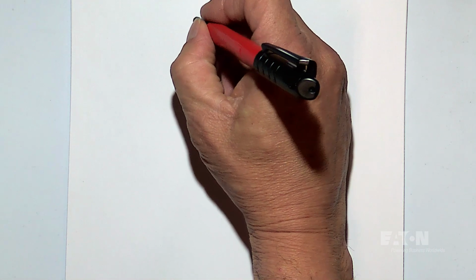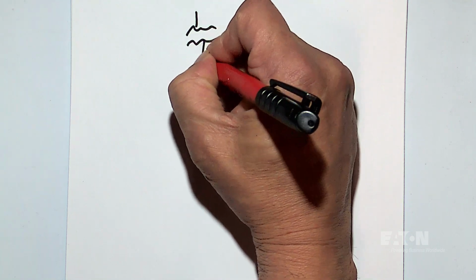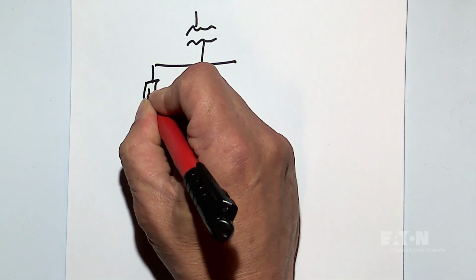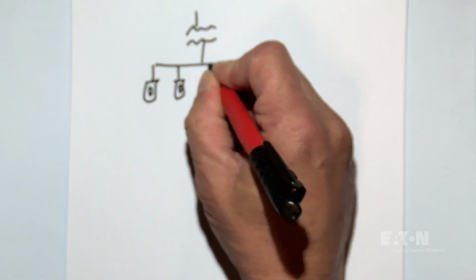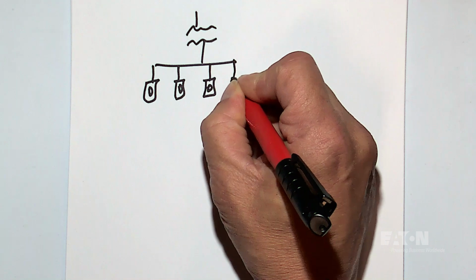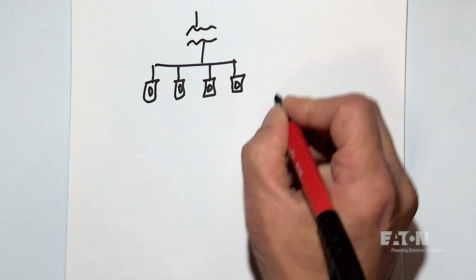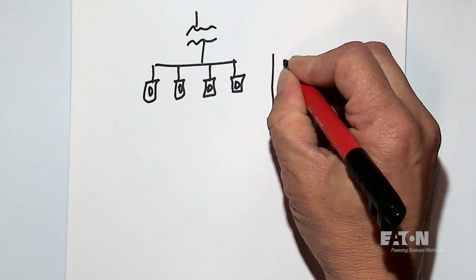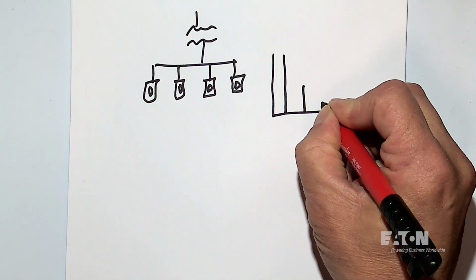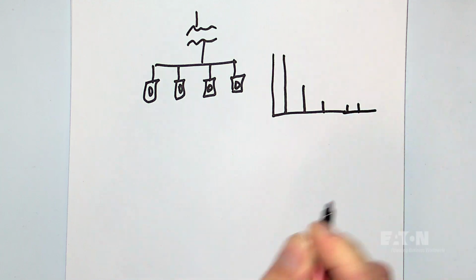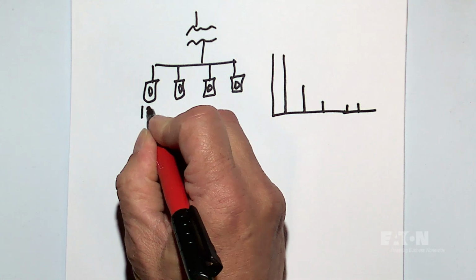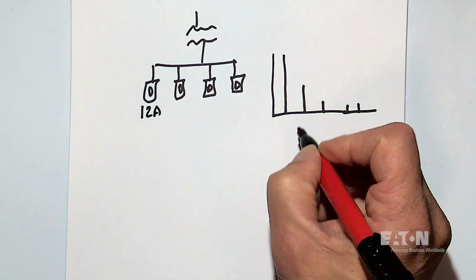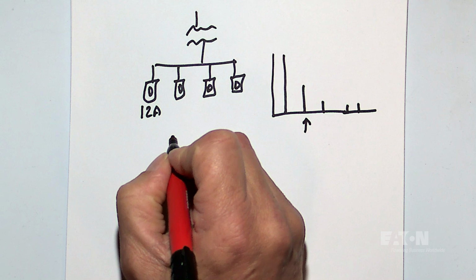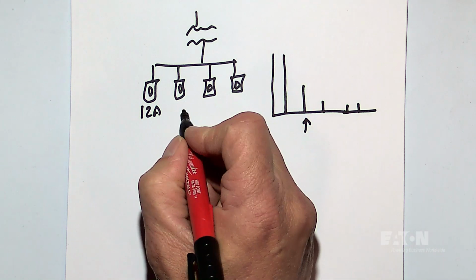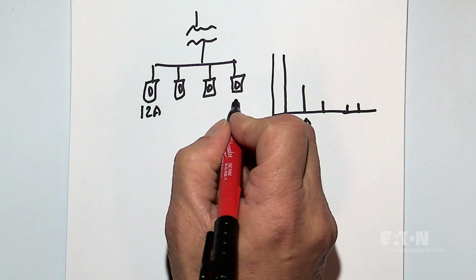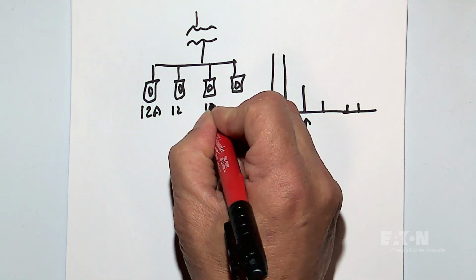So if we look at our power system and we have a transformer here, and let's say we have 4 drives. 1, 2, 3, 4. So we have 4 drives, and they all produce a spectrum of harmonics that we would expect for 6-pulse drives. So we have fundamental, 5th, 7th, 11th, and 13th, for example. If this one drive by itself produced 12 amps of 5th harmonic current, then we would expect that all 4 of the drives, if they're the same exact drive, would produce the same amount of harmonic current, and that would be the case if we did one drive by itself. So we'd say 12, 12, 12, 12.